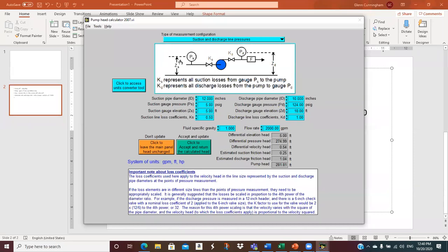The loss coefficients used here apply to the velocity head in the line size represented by the suction and discharge pipe diameters at the points of pressure measurement. If the loss elements are in different size lines than the points of pressure measurement, they need to be appropriately scaled. It is generally suggested that the losses be scaled in proportion to the fourth power of the diameter ratio. And when you start taking things to the fourth power, they get big pretty quick, or small pretty quick.